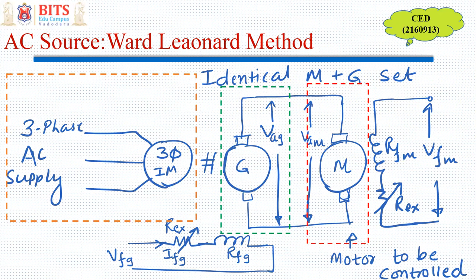This generator is driven by a three-phase induction motor using a three-phase normal AC supply, so it is a constant speed machine running the generator. The excitation of the generator is varied to change the output voltage VAG, which acts as the armature voltage input VAM to the motor. So by varying the excitation of the generator, I can vary the armature voltage — this is how armature voltage control is achieved.